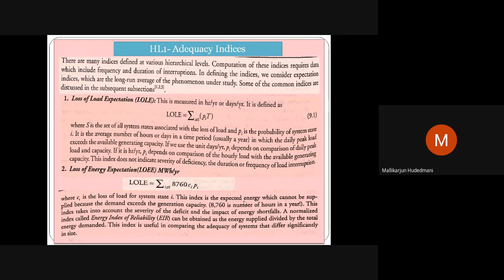This index is the expected energy which cannot be supplied because the demand exceeds the generation capacity. Now see, this is a very interesting factor. A certain generating plant has 5 generators. The total capacity of the generators is known to us. Due to a certain situation at a certain hour, due to a maintenance lack or the maintenance schedule, or due to an internal failure or a minor fractional failure, you cannot provide the capacity which is required for the meeting. At that time, this is the measure of that system at the max, at the worst possibility. My power system, the generator system, will not be able to cope for so many megawatt hours in a year. That's what is measured.